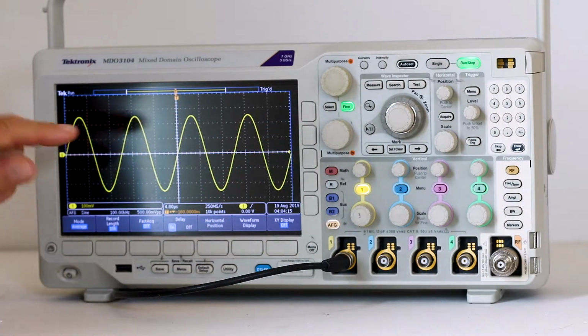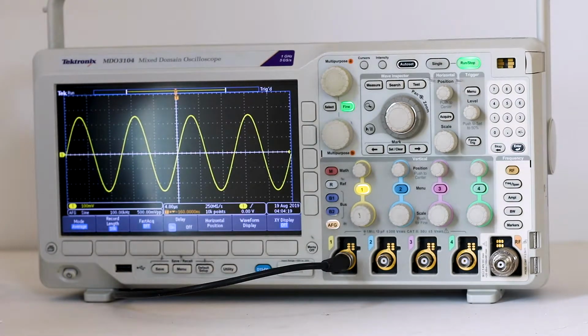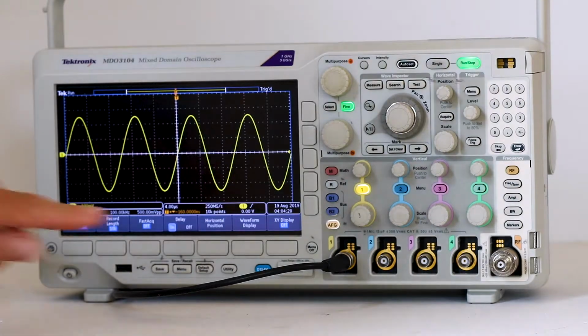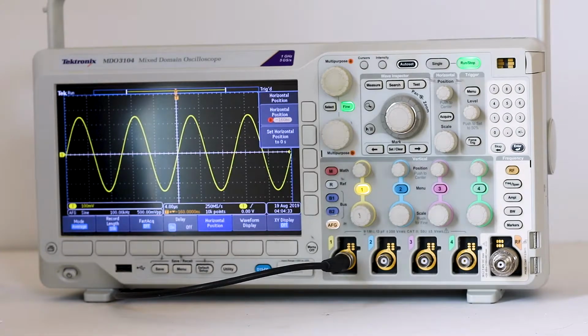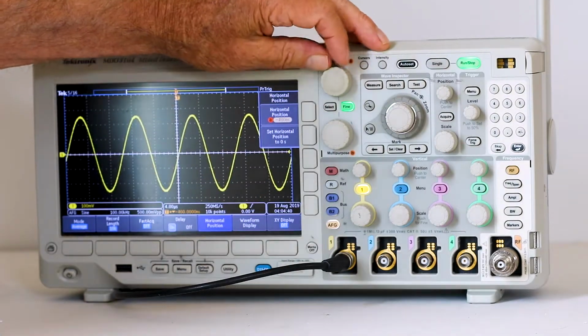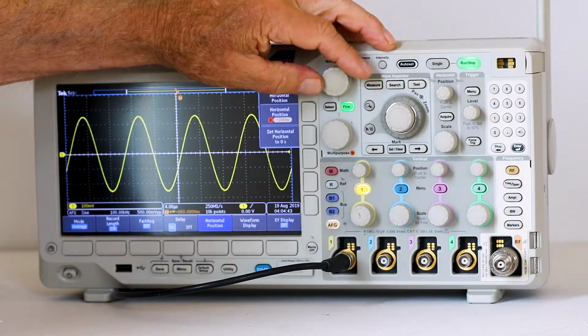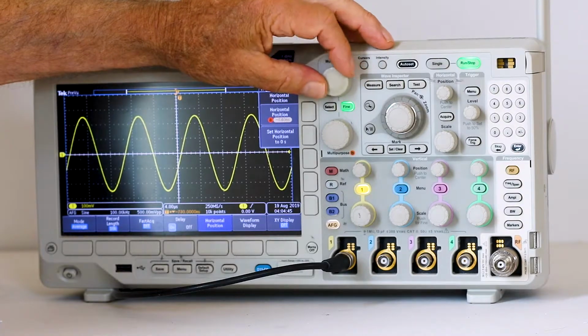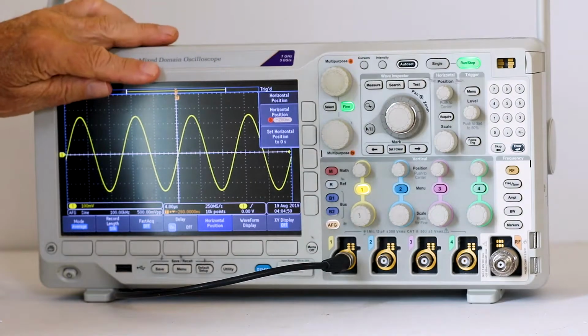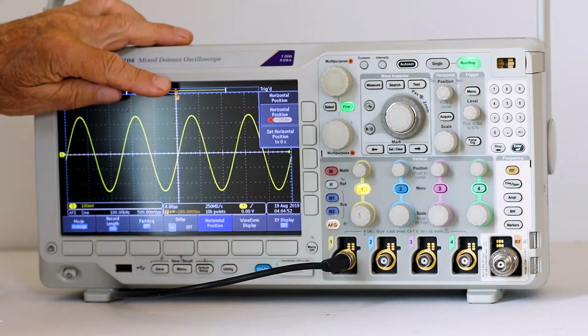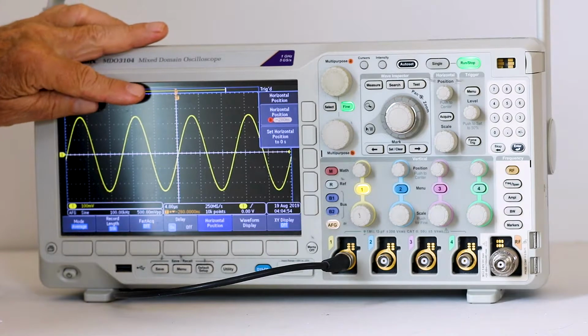Pressing the soft key associated with horizontal position in the horizontal acquisition menu, the vertical horizontal position menu appears. Then, using multipurpose knob A, the horizontal position can be set at a desired interval in time. Notice that if you do this, the trigger point moves horizontally away from its usual position corresponding to units of time on the x-axis.